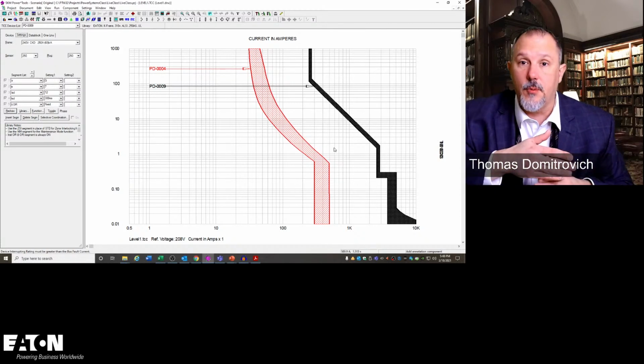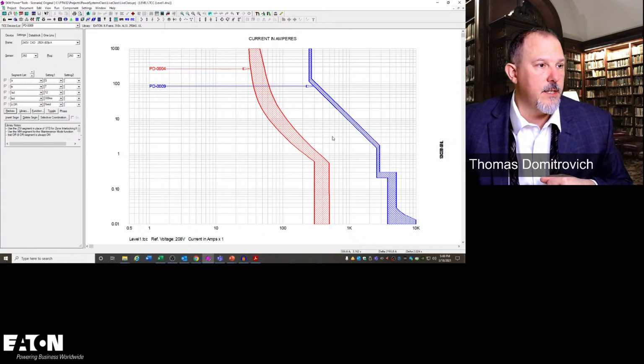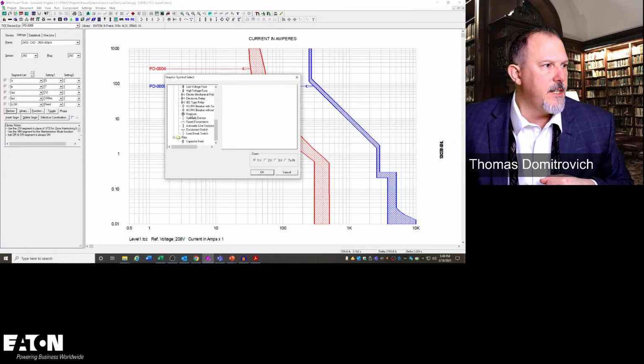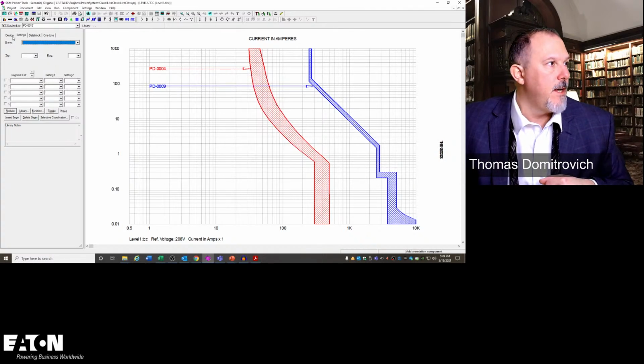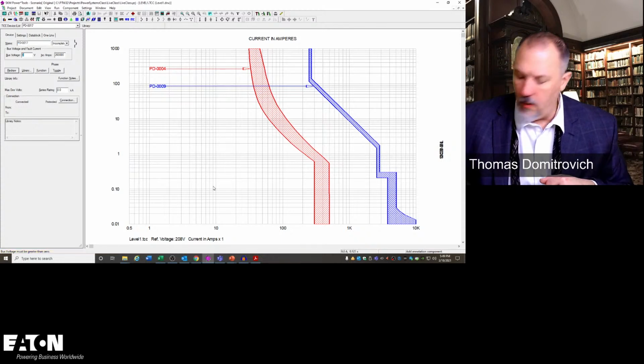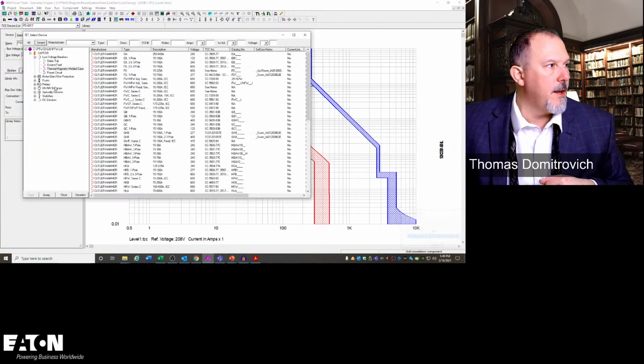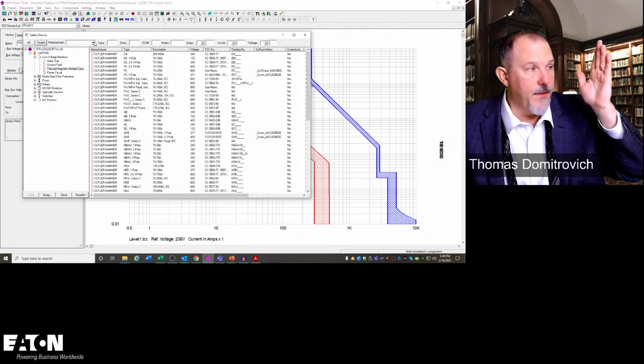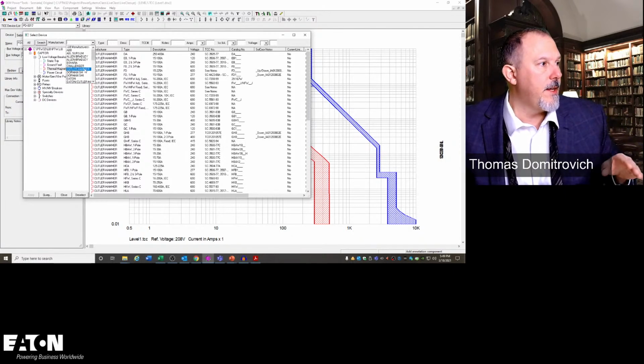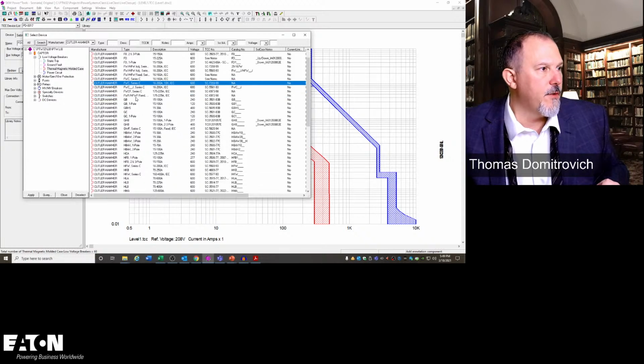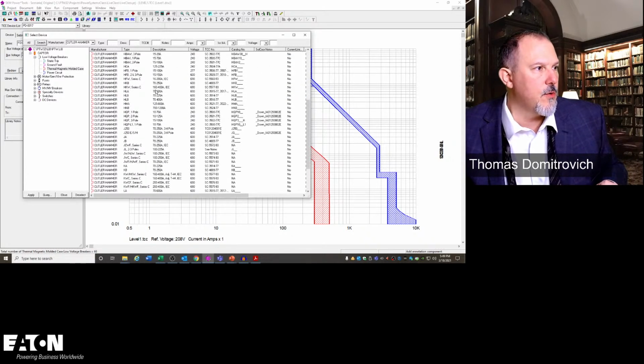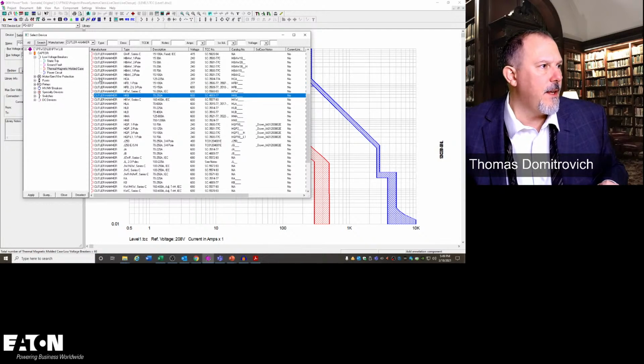Could I have put a different breaker in here? Maybe. Let's take a look. Let's add a different one. Now this is a 250 amp panel board. Let's go and grab a thermomagnetic circuit breaker. This is 208 volts. I'm going to go to the library, and I'm filtered on Eaton Cutler Hammer, so that's a good thing. I'm looking for a 250 amp breaker, right? So I'm going to scroll down here till I get to 2. There's an HKB 250. Oh, I got thermomagnetic. Okay, thermomagnetic, I need 2.